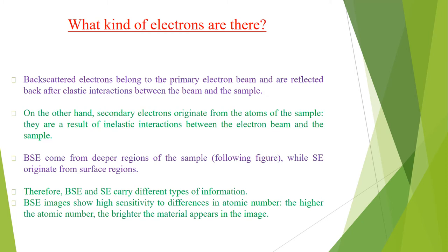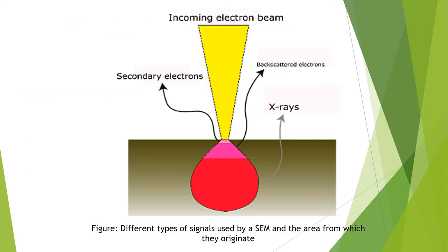Backscattered electrons come from deeper regions of the sample, while secondary electrons originate from surface regions. Therefore, backscattered electrons and secondary electrons carry different types of information. Backscattered electron images show high sensitivity to differences in atomic number — the higher the atomic number, the brighter the material appears in the image. A figure shows different types of signals used by the scanning electron microscope and the areas from which they originate.